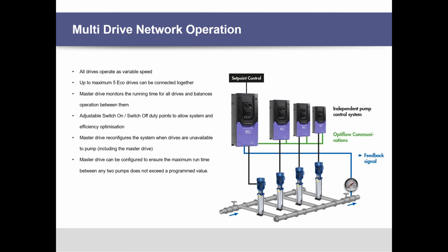We can have several drives working together to do booster pump applications. So duty assist, duty standby, duty assist standby, jockey pump type applications. So we can have self-contained systems just with feeding back a pressure signal to one drive, and then it controls the others.